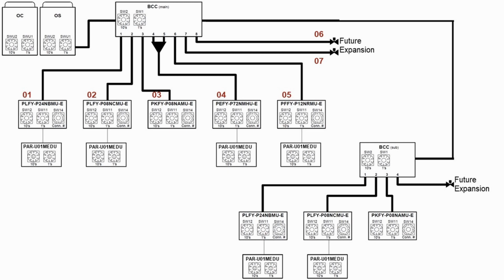So now that we know what the lowest addressed indoor unit is, let's do the outdoor units as address 51, 52, and the main BC controller would be 53. Since we left indoor unit addresses 6 and 7 for possible future expansion, let's address the units connected to the sub-BC controller as 8, 9, and 10. That would make our sub-BC address 50 higher than the lowest addressed indoor unit connected to it, or 58.